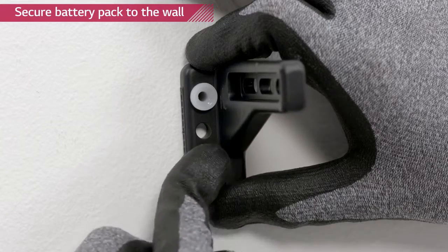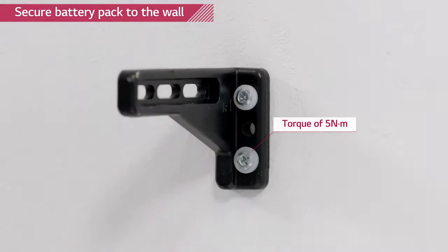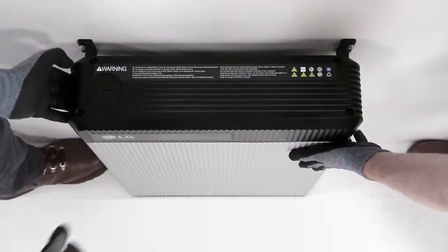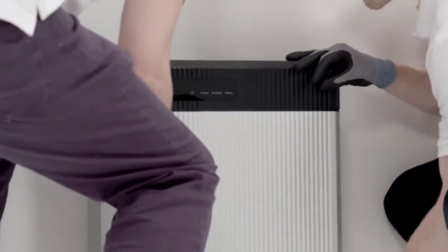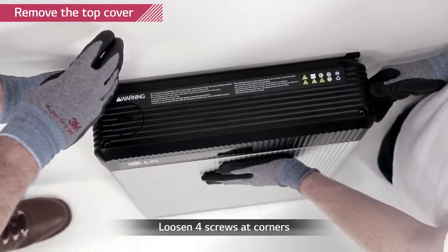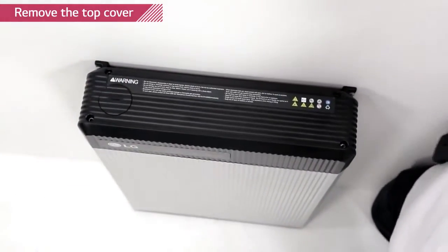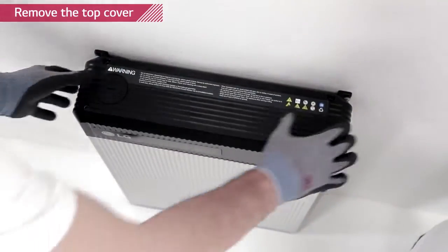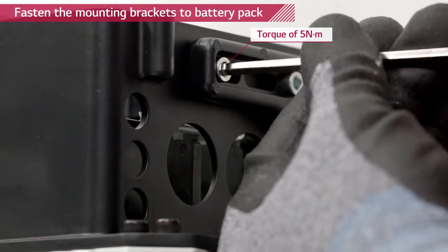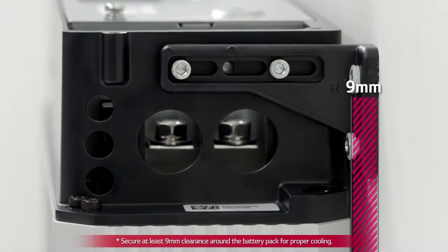Fix the provided mounting brackets to the wall with M6 screw anchors with a torque of 5 Nm. Place the RESU battery pack between the wall mounting brackets. Loosen the four screws on the top cover and remove it. Fix the RESU battery pack to the mounting brackets using M5 hex socket screws with a torque of 5 Nm. Remember that the battery pack needs to have a distance of at least 9 mm away from the wall.